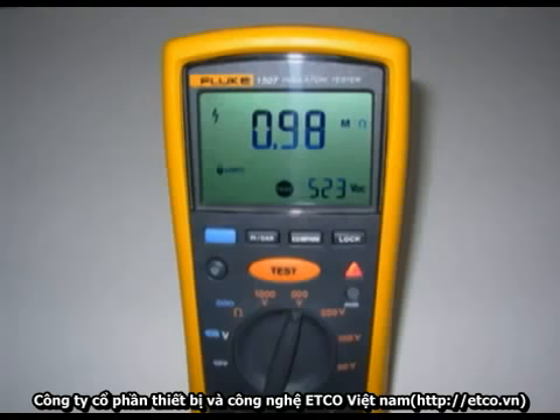So this test is complete. I've simply locked the results in so I could take the photo. It is, however, important to leave the test leads attached to the component being tested until the test has been terminated, as the high voltage will then be dissipated through the component and not dissipated through you.